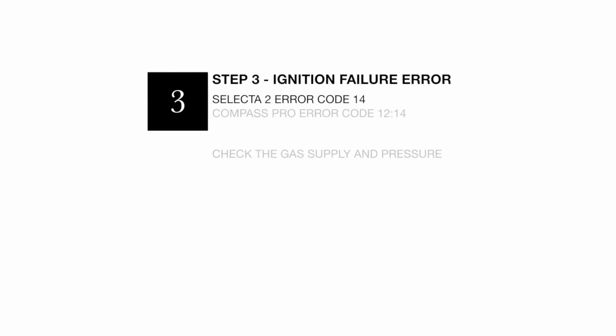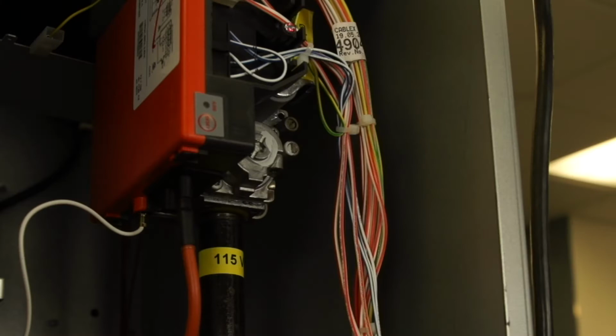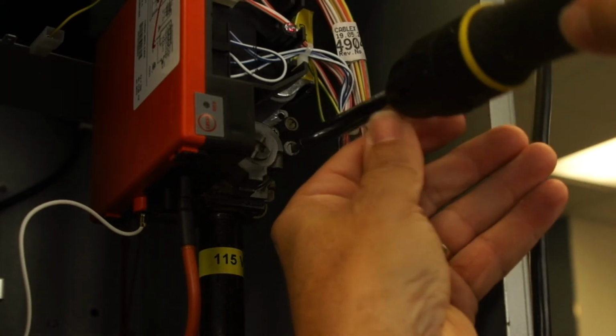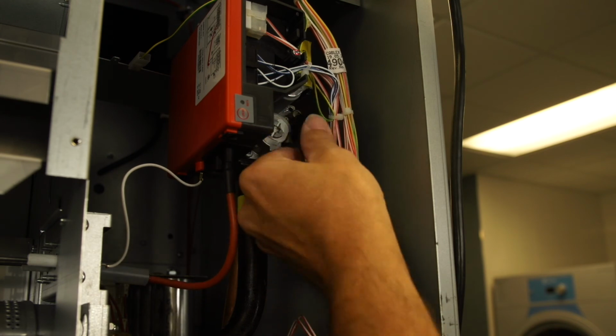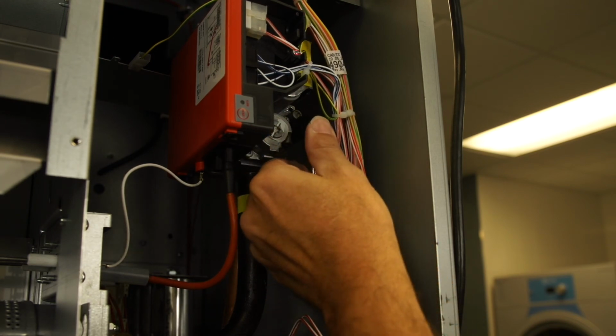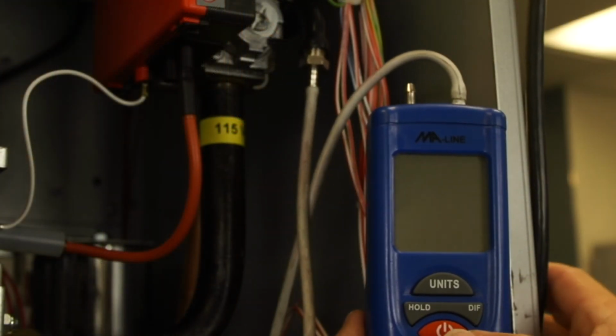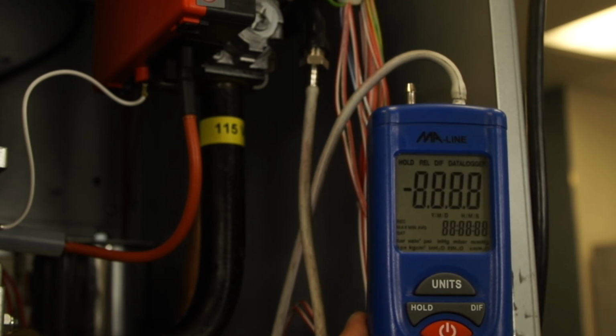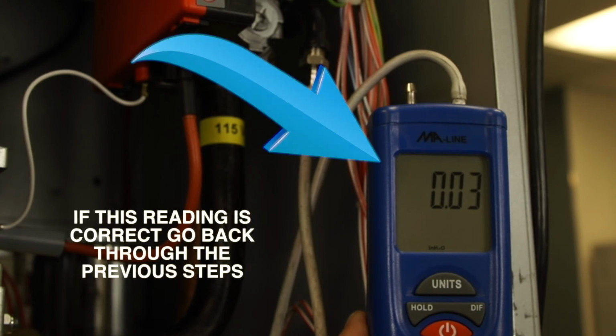In step 3, we'll be checking the gas supply and pressure. Use your manometer to check the gas pressure on the supply side and the nozzle side. You must do this during an ignition attempt. Based on our previous tests, you should be seeing a problem with the readings on your manometer. If your manometer readings are correct, we recommend reviewing the steps we've previously covered in this video.